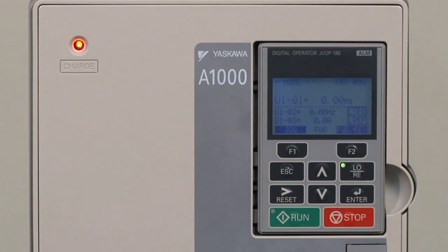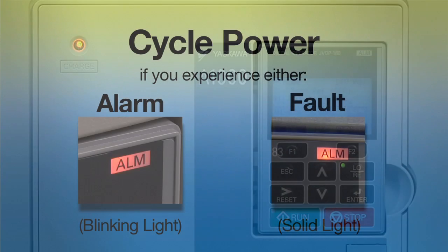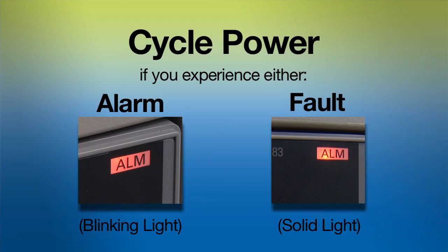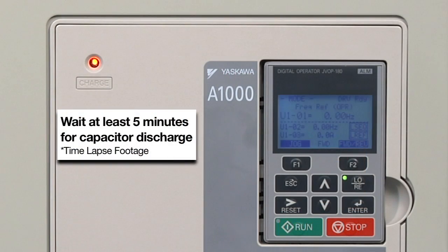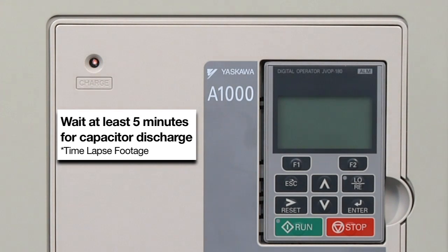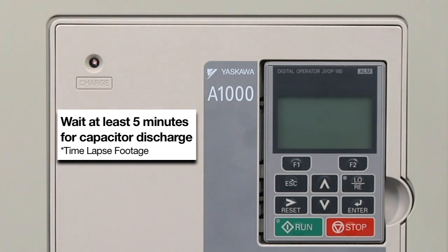Now, when you power up after flashing, make sure the system indicates no alarms or faults. If an alarm or fault arises, cycle power to the drive once again. Cycling power too quickly can often cause an alarm or a fault. So, be sure to leave the drive powered off until the charge light is completely extinguished. If you aren't certain, wait a while longer.